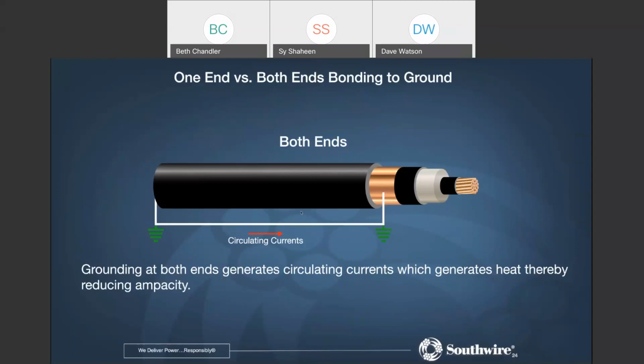But then if you want to ground them at both ends, again, the same scenario, but now I've grounded at both ends. You still have that transformer effect, though now you have what you call circulating currents. Yes, this is at ground potential, I get it, but you still have circulating currents. And because this tape shield inherently has a resistance, you get the I²R going in there, and that heats up the cable. When you heat up the cable, that means you get less ampacity.